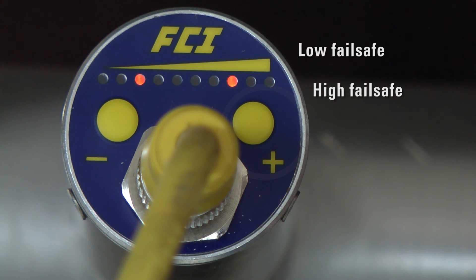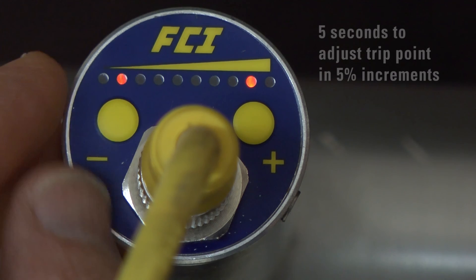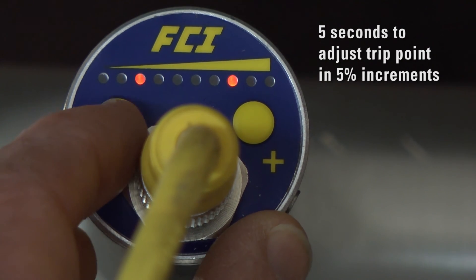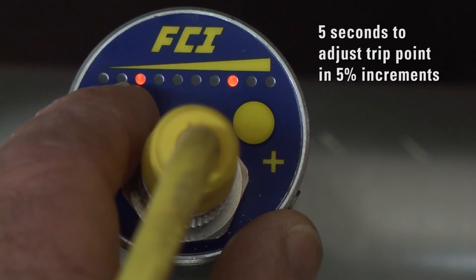The default alarm setting in this mode is 30% of the range. However, the operator has 5 seconds to adjust the trip point in 5% increments either up or down using the buttons.